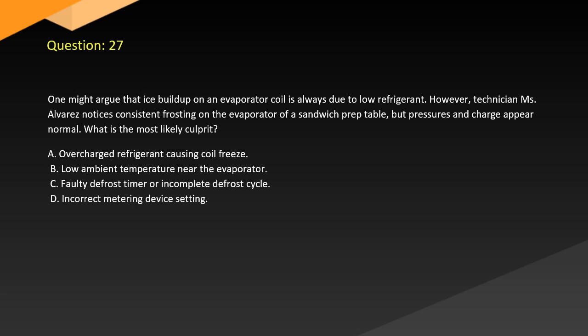Question 27. One might argue that ice buildup on an evaporator coil is always due to low refrigerant. However, technician Alvarez notices consistent frosting on the evaporator of a sandwich prep table, but pressures and charge appear normal. What is the most likely culprit? A. Overcharged refrigerant causing coil freeze. B. Low ambient temperature near the evaporator. C. Faulty defrost timer or incomplete defrost cycle. D. Incorrect metering device setting.